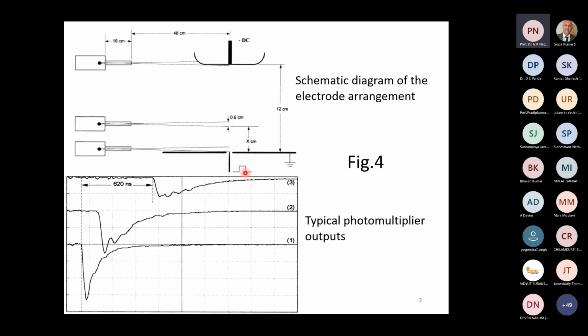As we'll see later, this needle will be fed with a rectangular pulse of 4 kilovolts, of two different durations: 270 nanoseconds and 135 nanoseconds. We will be concerned with the 270 nanoseconds, the best case we can imagine from the ESE rod manufacturers. This ground plane has a trigger electrode—we'll call it the trigger electrode—and the trigger voltage appears between the needle and the plane.